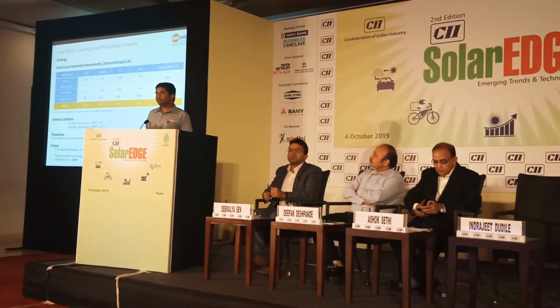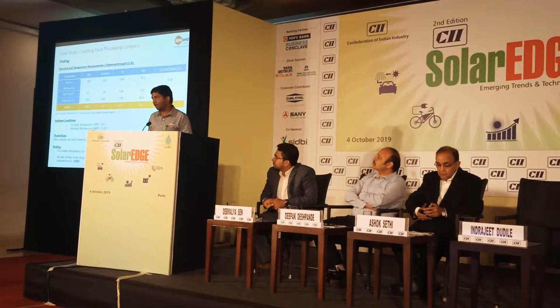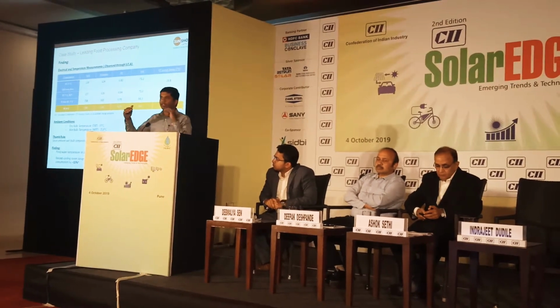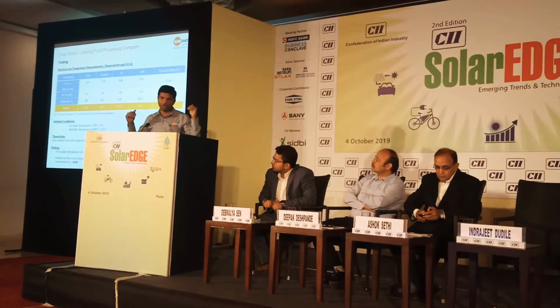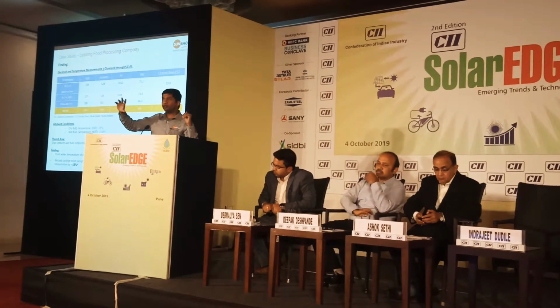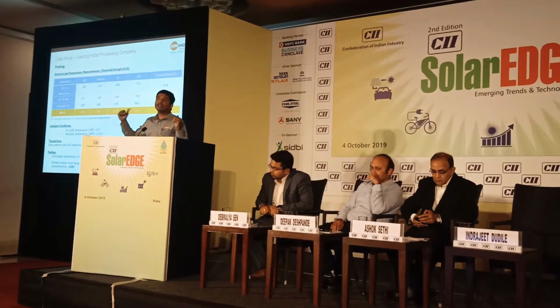So, for example, if I have 4 units to be consumed for every 1 unit of a product that happens on the production line, and that is the designated or design-specific consumption, software can monitor how electricity consumption is happening against that specific energy consumption point. If there is a 5% variation allowed, you can set an alarm so that if your specific energy consumption varies beyond 5%, so-and-so person has to get the alarm.